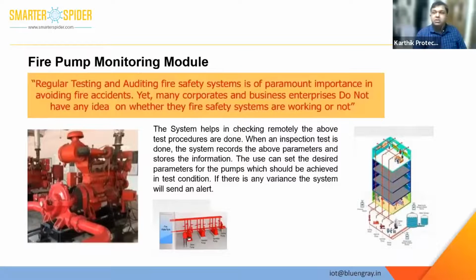The requirement for this module came from our surveys and installations, where we found that the fire pump systems in hospitals, in most cases, are either kept in manual mode or in off mode. In some cases they are kept in auto. And we also found in one case that there was pilferage of diesel from the diesel pump.